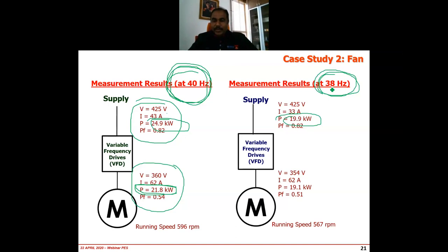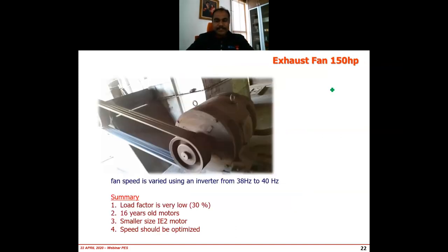Okay, so what we suggest in this case is, of course, it's a good thing. We say you must optimize the frequency, see whether you can reduce further. Number two, the motor is completely oversized. If you can reduce the size of the motor, probably you can have better efficiency. You can further reduce the kilowatt in this case. Right? So this is the exhaust fan that I mentioned just now.